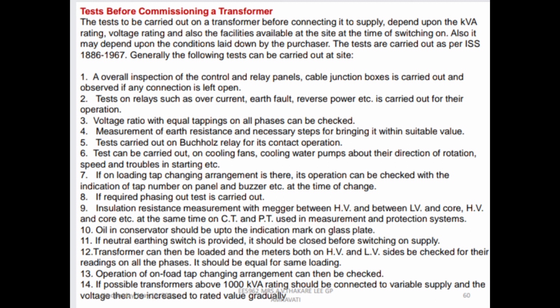The tests to be carried out on a transformer before connecting to the supply depend upon the kVA rating, voltage rating, and also the facilities available at the site at the time of switching on. Also, it may depend upon the condition laid down by the purchaser. The tests are carried out as per IS 1886 1967. Generally, the following tests can be carried out at site.